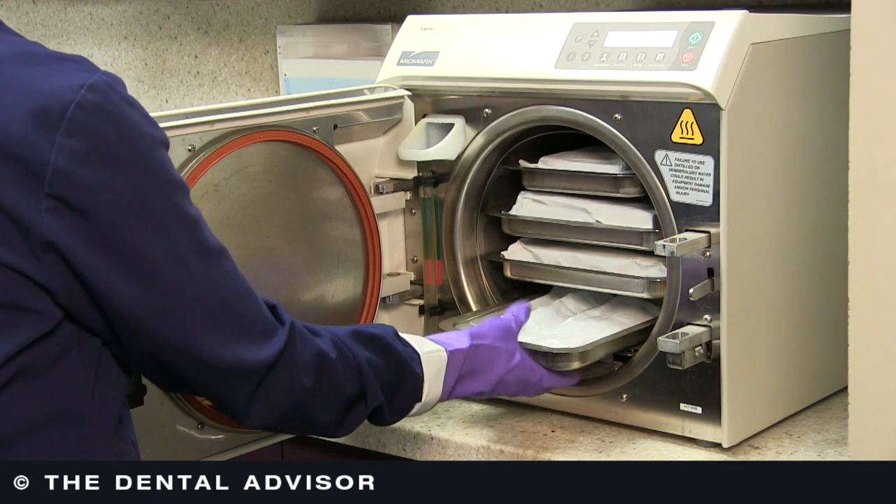You mentioned that they need to be dried — why do we have to dry them if we're just going to put them in a steam autoclave anyway? If you leave instruments wet, they can actually acquire white deposits. Also, one of the reasons for sterilization failure is taking wet packs out of the sterilizer. As soon as you take them out wet, they're subject to wicking, which means microorganisms can go through the wet packaging.